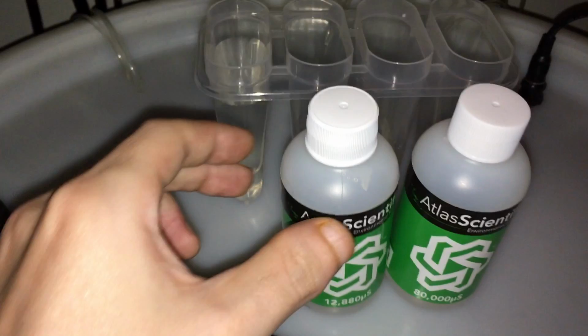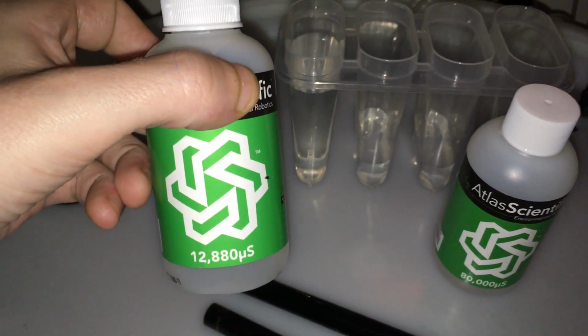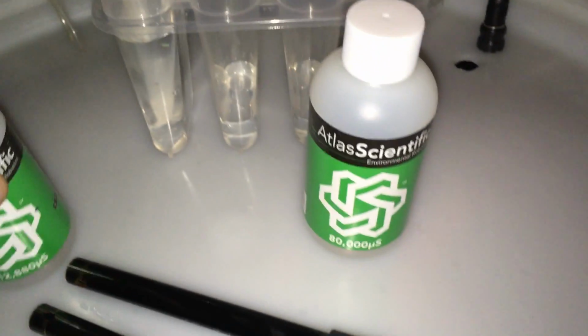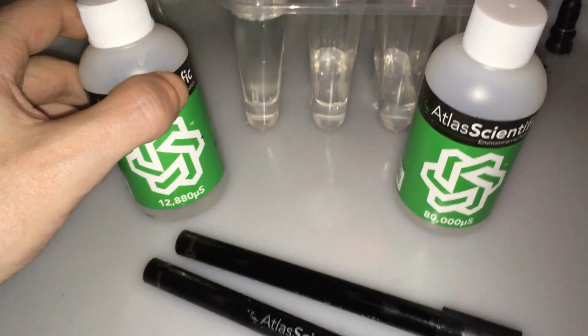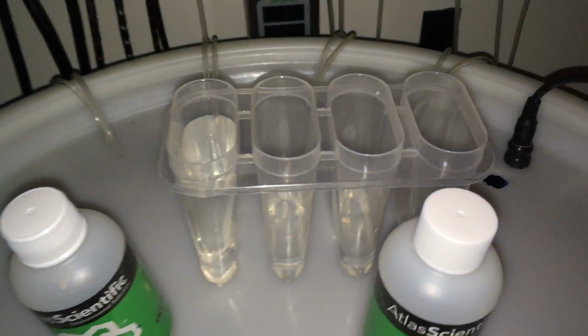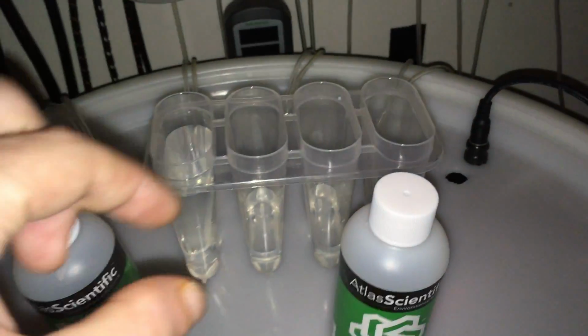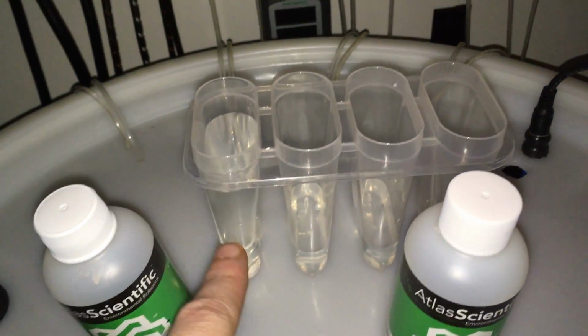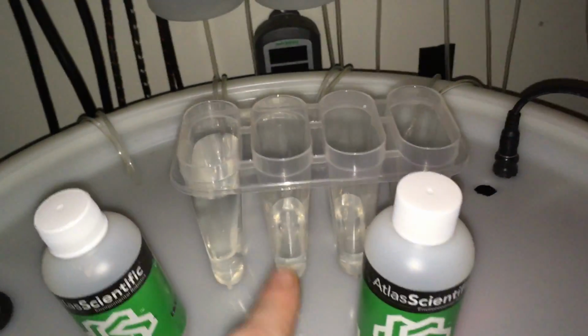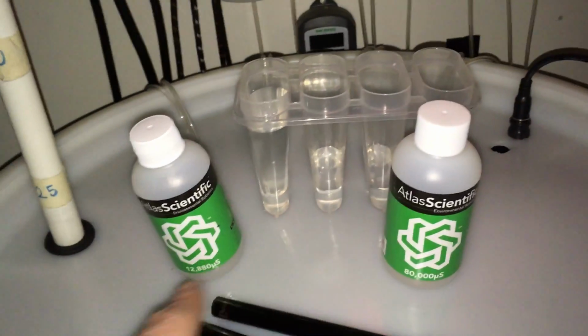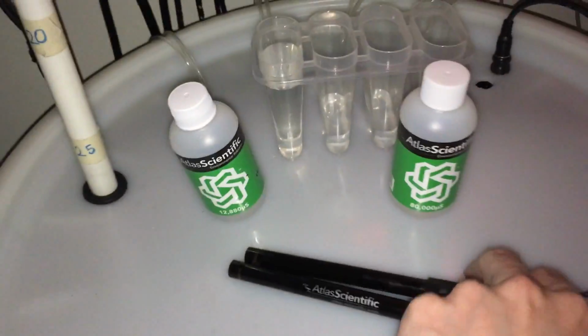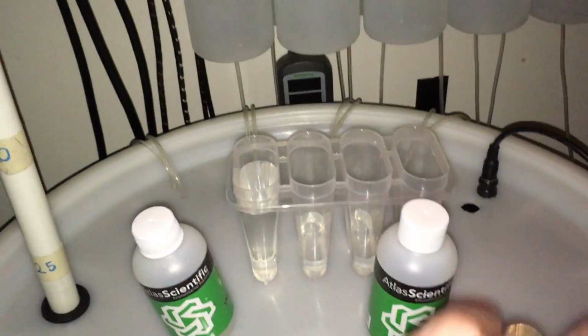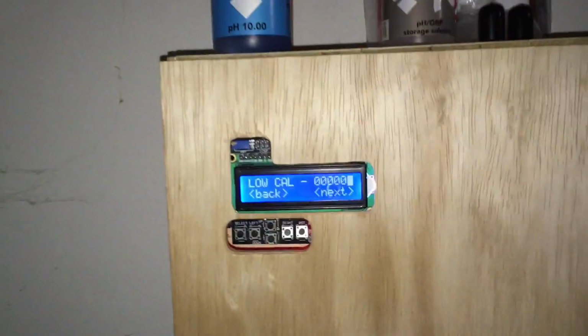Okay, so what I have right here is a 12,000 and an 80,000 solution, and I use this popsicle mold because it's a lot easier than using little cups. I filled up one chamber with water, and then the other 2 chambers with these different solutions. And the calibration that we just did is the dry calibration, which is out, and then we're going to dip it into our low calibration solution now.